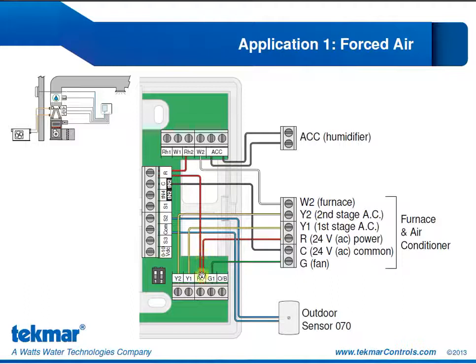Now let's trace these wires. We have our 24 volt R coming from the unit into the 557, connecting up here to the R, and that's being jumpered to RH2, which is connected to the W2, and then back to the furnace. Y1, Y2 are straight connections over to the 557, as is our G, and our common is going straight to the common on the 557.